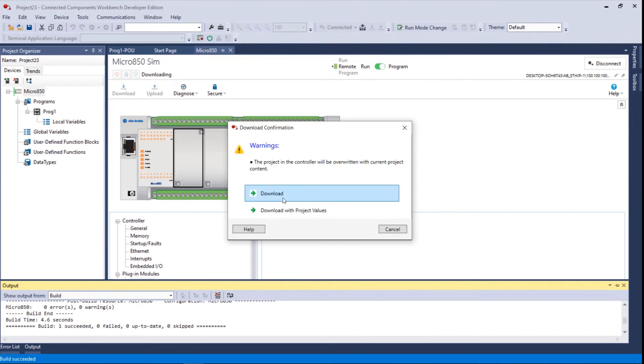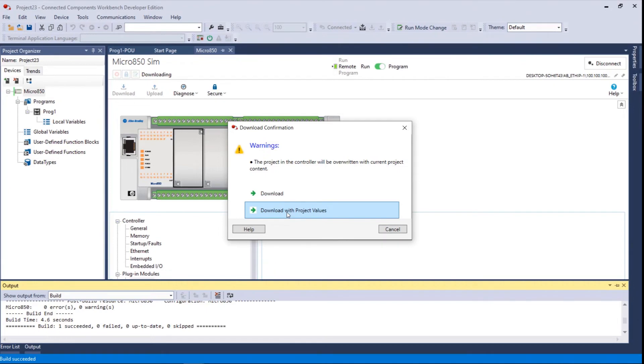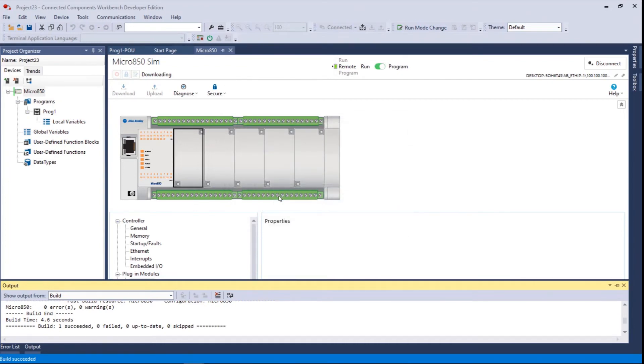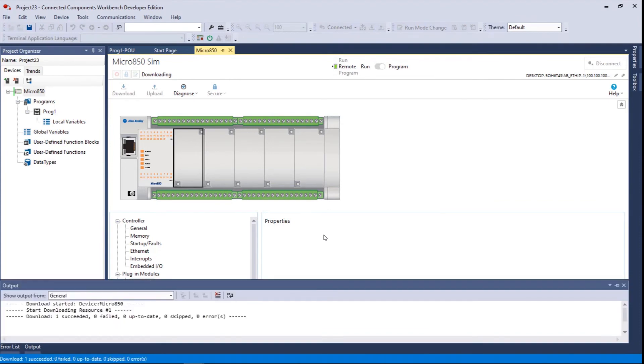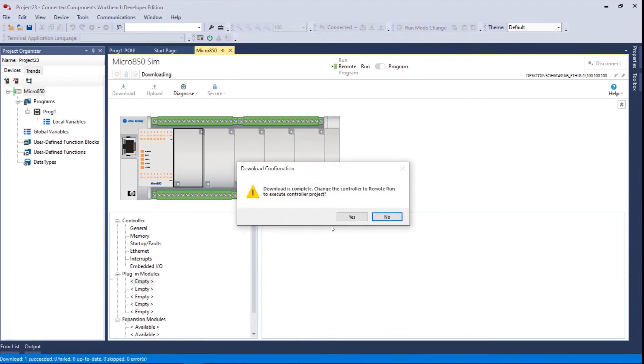When this dialog comes up: 'Download' versus 'Download with Project Values.' Project values are values in registers like timer accumulators and math instructions — we don't have any yet. A plain download is faster, and you also have to consider that if you have an offline database and an online database, downloading with project values could overwrite values in the controller you didn't want to change. So I'm going to select 'Download.' You can see: downloading project file, build started, download succeeded, download is complete.